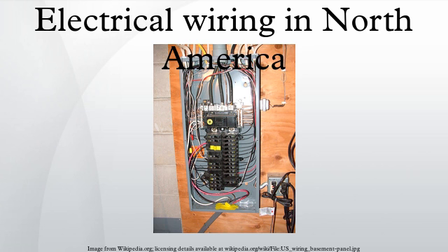The most common residential and small commercial service in Canada and the US, single split phase, 240 V, features a neutral and two hot legs, 240 V to each other, and 120 V each to the neutral. The most common three-phase system will have three "hot" legs, 208 V to each other and 120 V each to the neutral.